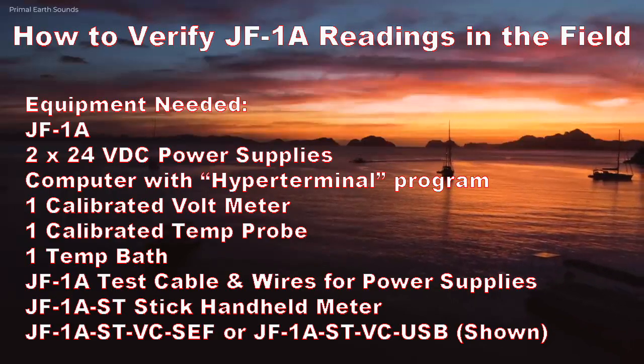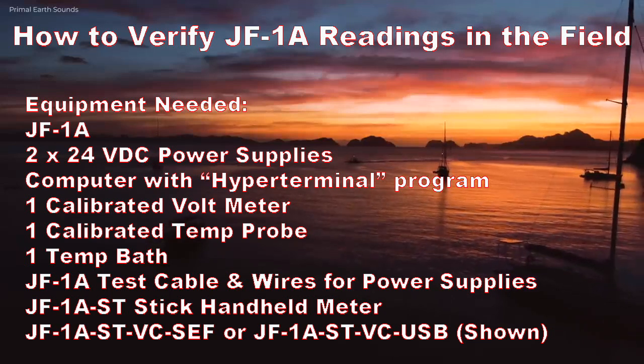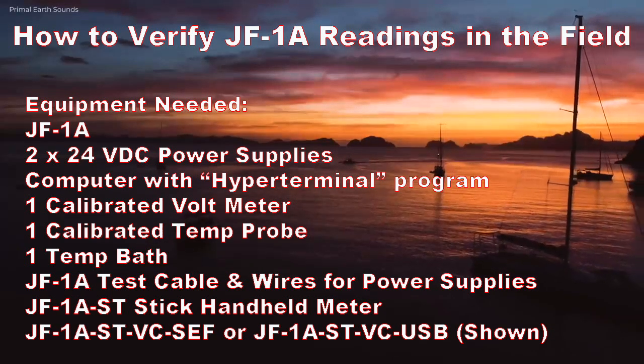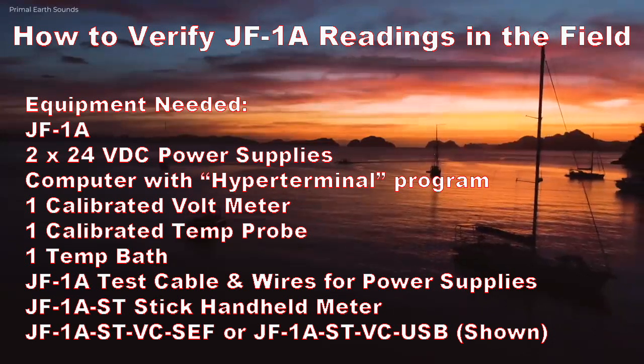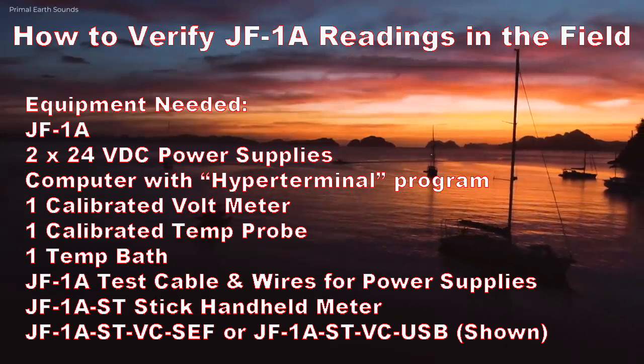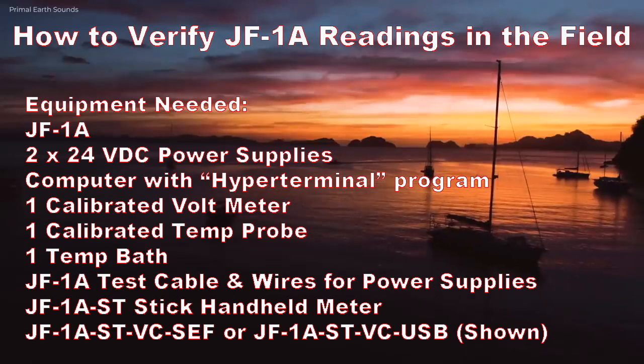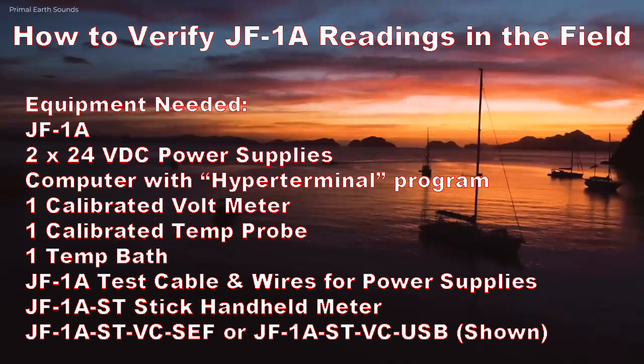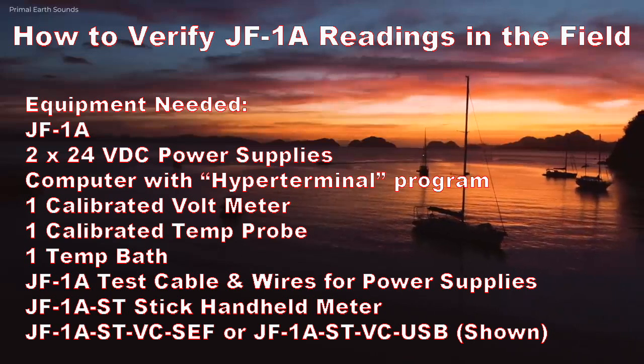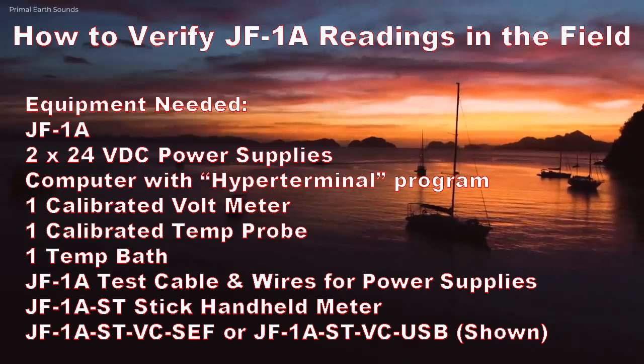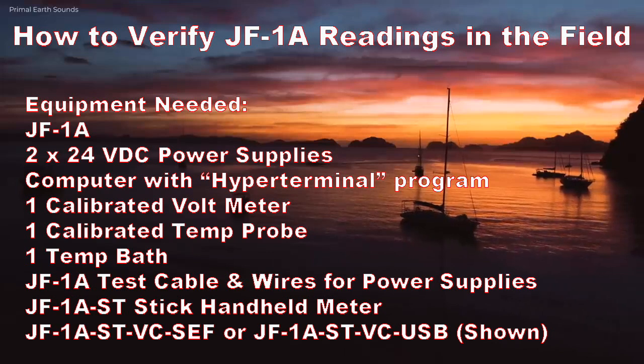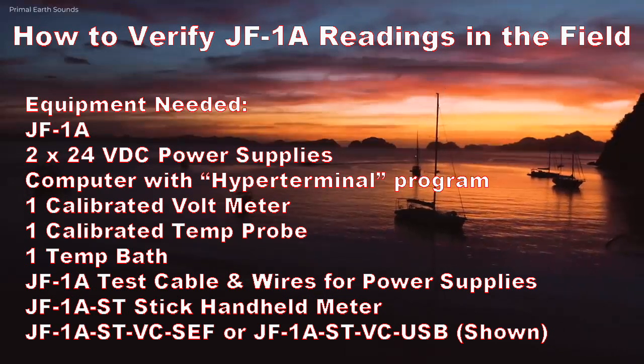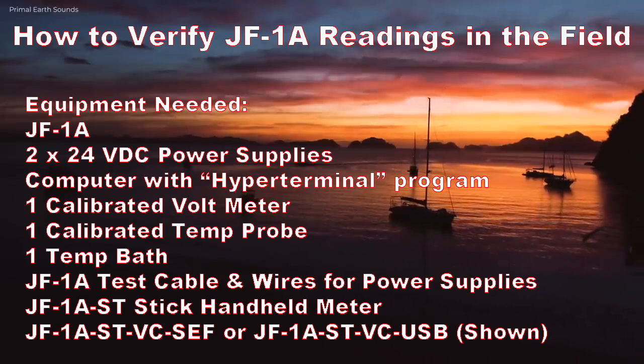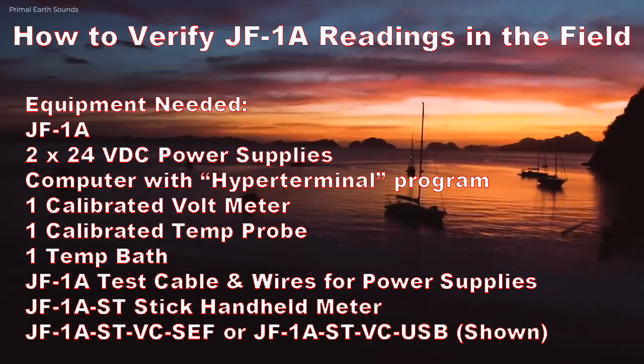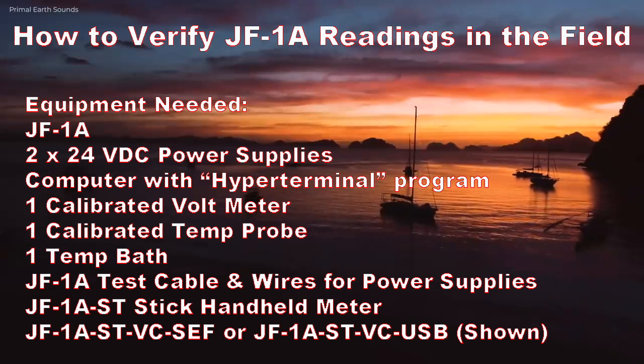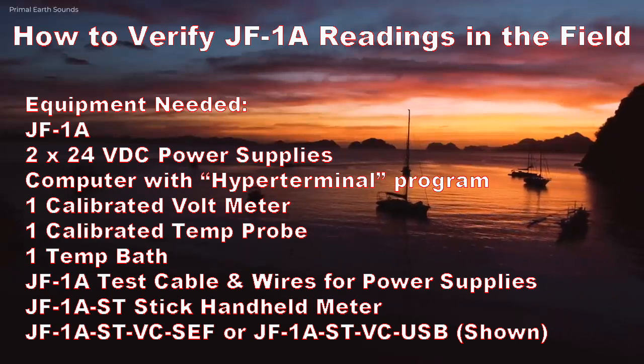In this video, we're going to be showing you how to verify and how to calibrate the JF-1A inline sensor in the field using the D-2 calibration kit that we are selling, which includes two 24-volt power supplies, calibrated voltmeter, calibrated temp probe, JF-1A test cables and wires for the power supplies, a JF-1A ST stick handheld meter, and the JF-1A STVC SEF calibration box, or the JF-1A STVC USB, which is a calibration device shown in this video.